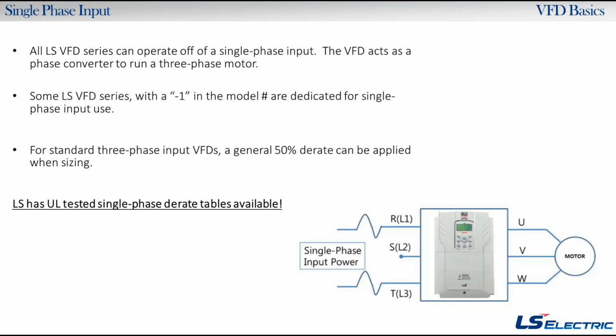Okay, but let's say you need something higher than 3 horsepower. If you're going to do something higher than 3 horsepower, let's say 20 horsepower, you would need to run a 20 horsepower motor, but you only have 230-volt single phase in. Well, you would need a 40 horsepower drive, because in general there's a 50% derate. That means you double the size of the drive. I say general because we actually had all of this UL tested. Let's just note down here, UL tested single phase derating tables are available. If you have your price sheet, or I think we also published this in the manuals and the product brochures, I would use that to check what the exact derate is, but it's about 50%.